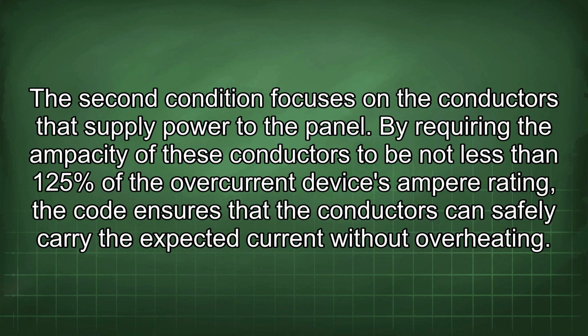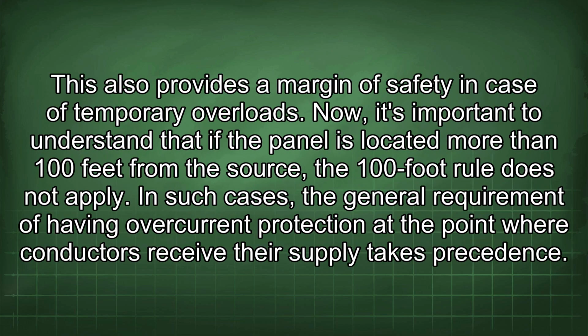The second condition focuses on the conductors that supply power to the panel. By requiring the ampacity of these conductors to be not less than 125% of the overcurrent device's ampere rating, the code ensures that the conductors can safely carry the expected current without overheating. This also provides a margin of safety in case of temporary overloads.